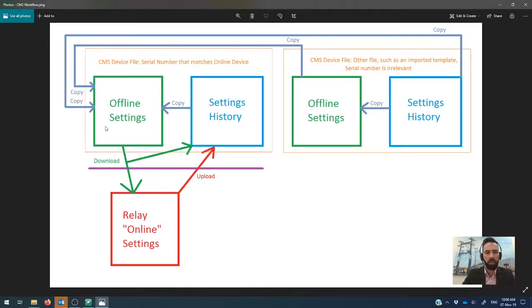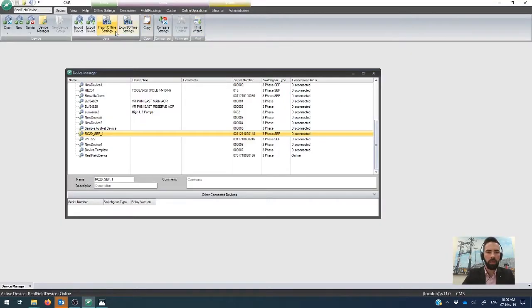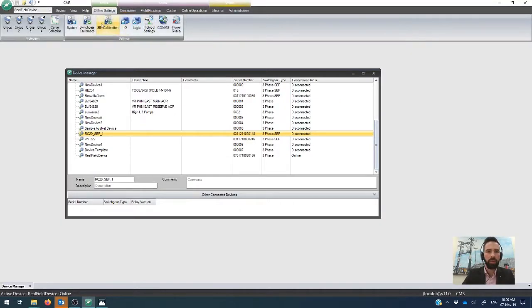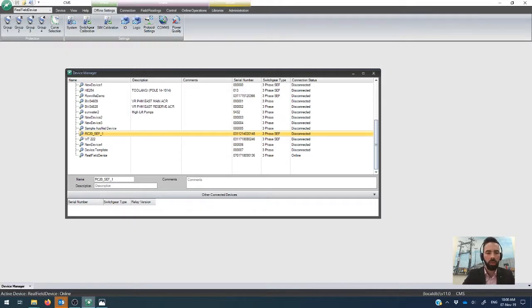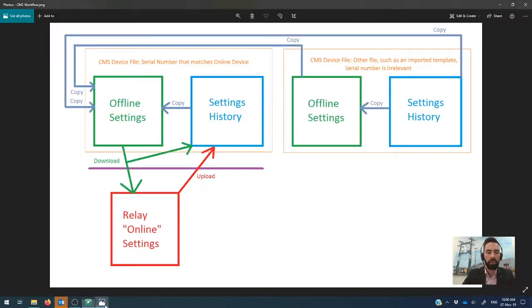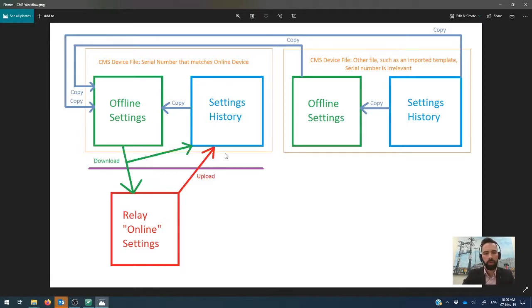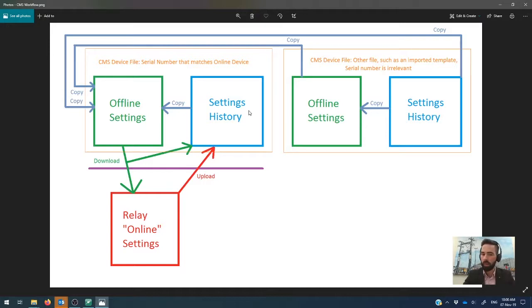So in the system, we have both offline settings, which if I click back over here, lives in this tab on this side. So these are things that you can modify and put into the controller. But if we go back, we can also see that there is a settings history. And this is a log of everything that's ever been done, all the settings that have been uploaded or downloaded into the controller in the field.